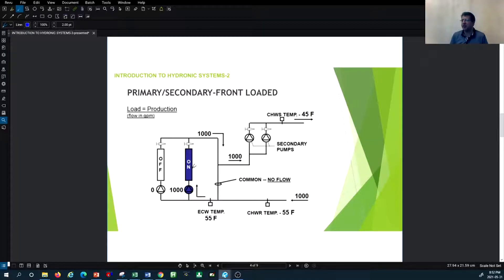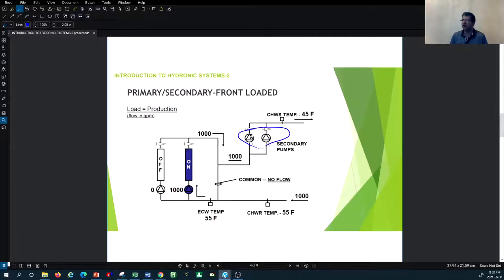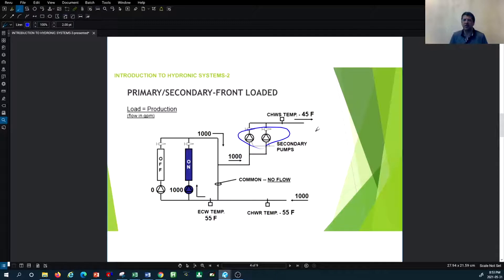On the secondary side, you have secondary pumps running at a maximum capacity of 1000 GPM total — each pump handling 500 GPM. The secondary and primary loads are the same in terms of load and production. In this case, because the supply is at 45°F, we are providing chilled water, since that is the range of chilled water supply temperature.